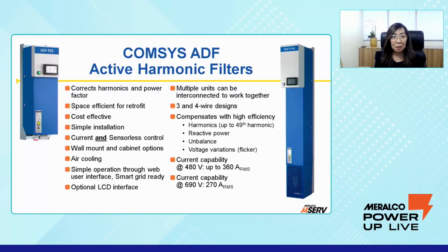So let me talk a bit about it a little further. It's called the ComSys ADF, and it corrects harmonics and power factor. And it's very space efficient. If you notice on the photo, it's quite slim. So if you have an existing facility, this is very easy to install. It's also very simple to install, and it has current and sensorless control. You can either mount it on the wall or it has cabinet options, and it just requires air cooling, no air conditioning required. It has a web user interface, very easy to use, and it's smart grid ready.